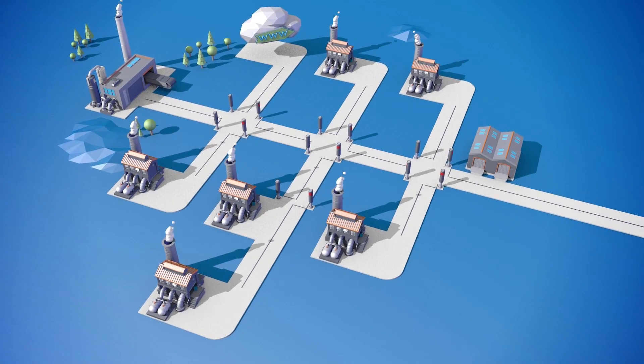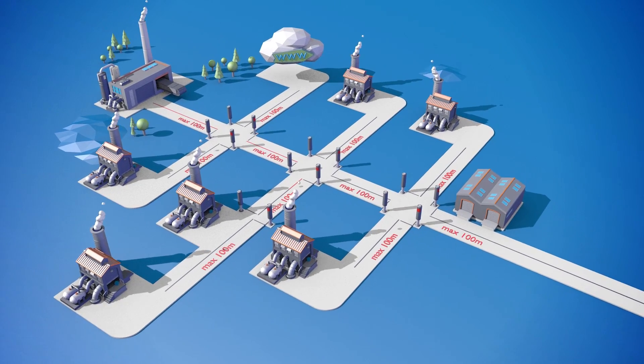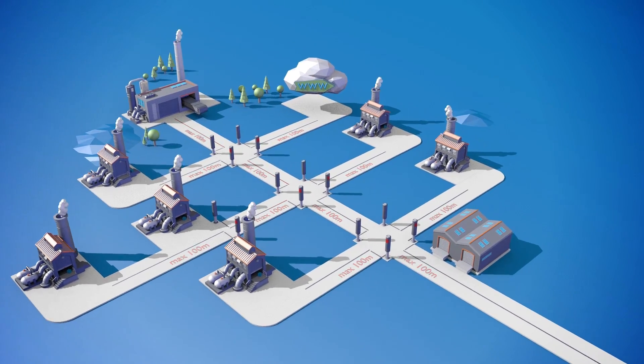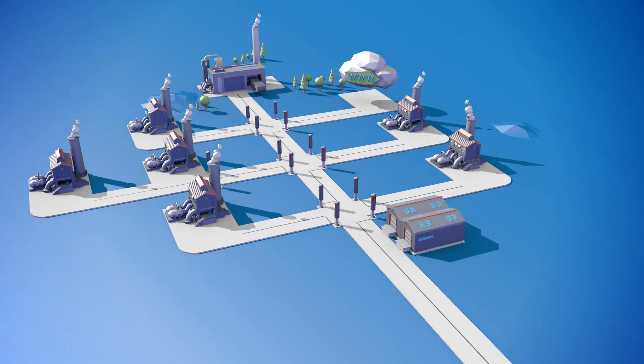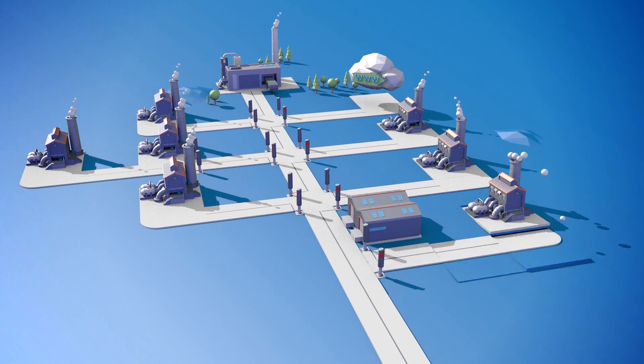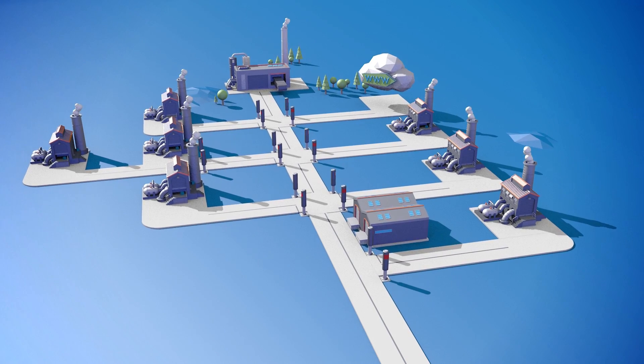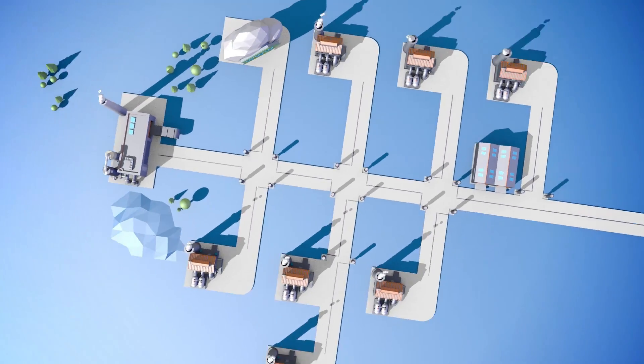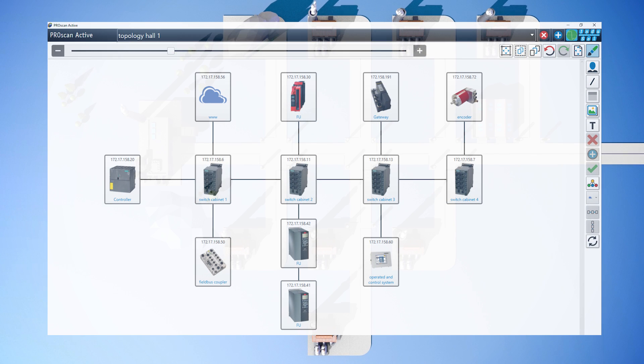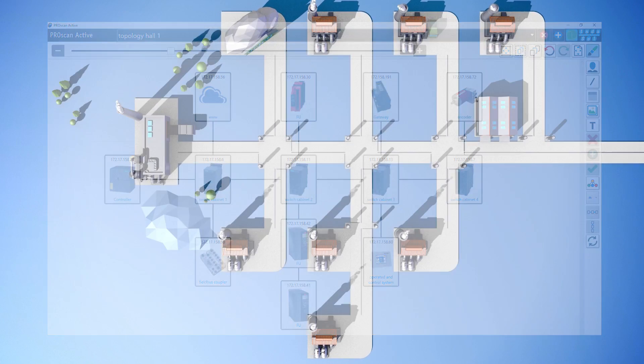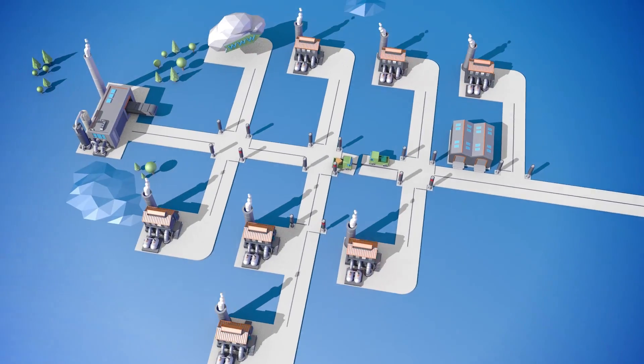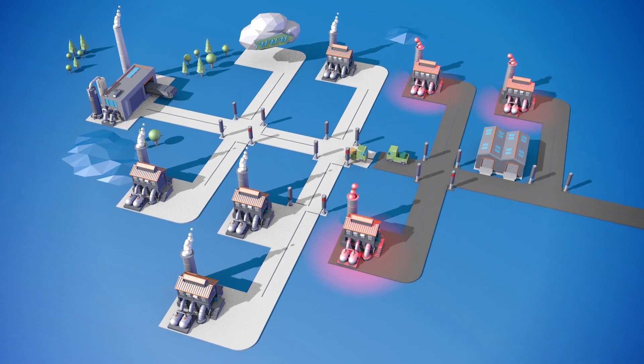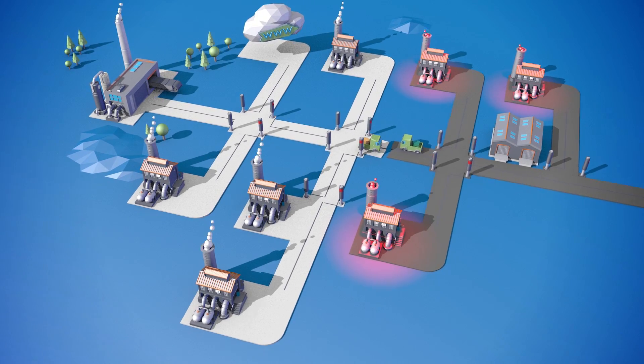Cable lengths of max 100 meters between network nodes provide reliable data transmission. The Profinet technology makes it possible to change structures in a breath. Constant monitoring in the form of an up-to-date topology plan is therefore essential. The overview of the actual wiring enables any connections between the network structure and a diagnosed error to be detected much faster.